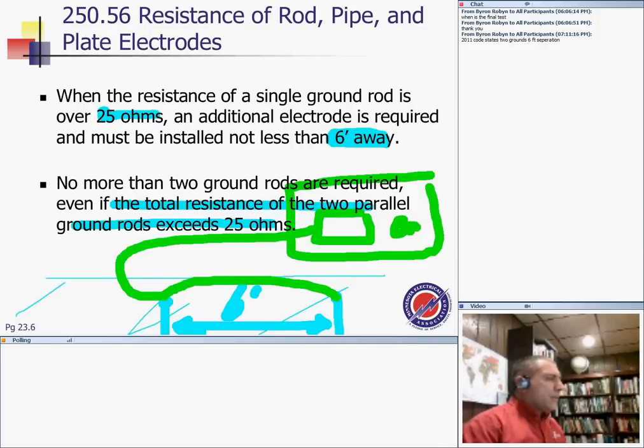So that's in 2011. They changed it. They say the default is having 2 unless you prove that you can get 25 or less. So they put the ball in your court to buy equipment to prove it. And how many are going to buy equipment to prove it? None. So you just tie to the 2 rods. And even if these 2 are there, guys, you have to tie to them anyway. So it's not like you're off the hook. If they're there, you have to tie to them anyway.